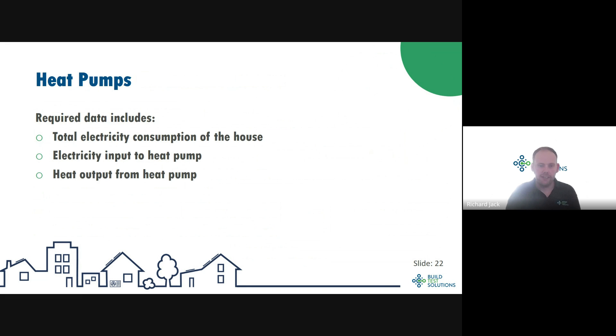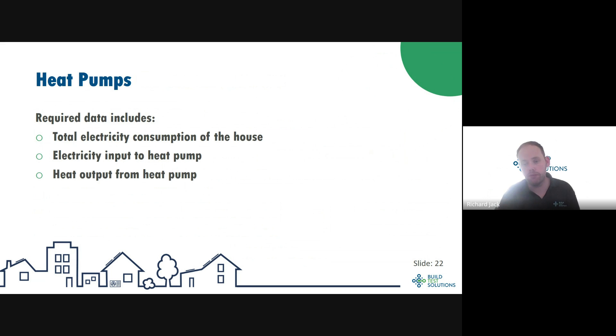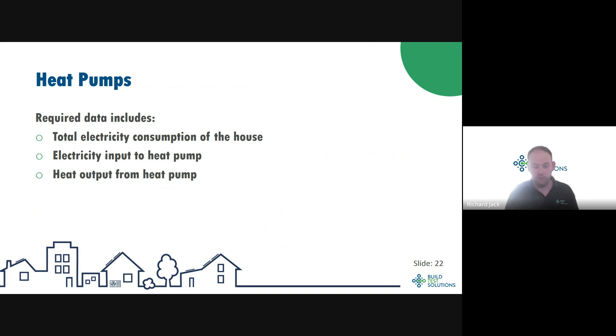For heat pumps, we want to know the total electricity consumption of the house as always, but we also need the electricity input to the heat pump and the heat output from the heat pump. That's because the performance of heat pumps is really variable with outside conditions and can also vary with the quality of the installation.